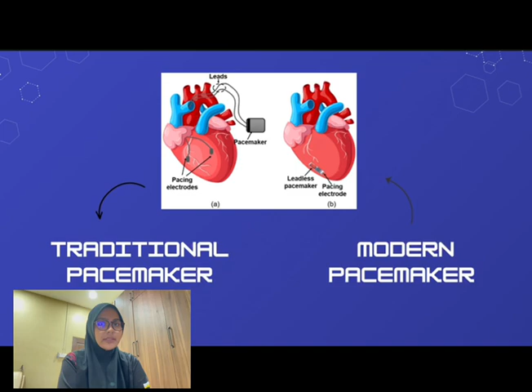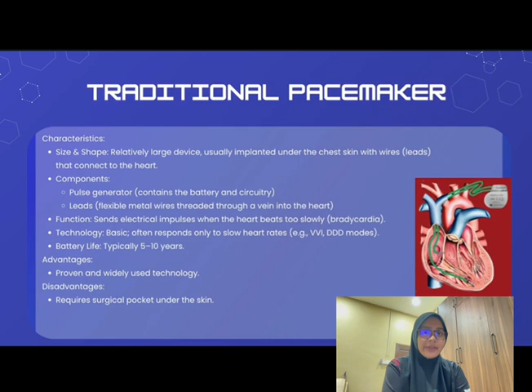So here's the pacemaker. The first one is the traditional pacemaker and the second one is the modern pacemaker. For the traditional pacemaker, for the size and shape, it is a relatively large device, usually implanted under the chest skin with wires that connect to the heart. The components are a pulse generator and leads. For the function, it sends electrical impulses when the heart beats too slowly. The technology very often responds only to slow heart rates. The program settings are adjusted externally by the doctor using a programmer. The battery life is typically 5 to 10 years.